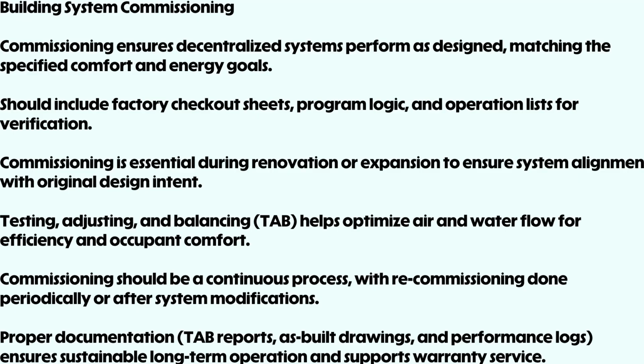Building system commissioning. Commissioning ensures decentralized systems perform as designed, matching the specified comfort and energy goals. Should include factory checkout sheets, program logic, and operation lists for verification. Commissioning is essential during renovation or expansion to ensure system alignment with original design intent. Testing, adjusting, and balancing, TAB, helps optimize air and water flow for efficiency and occupant comfort.